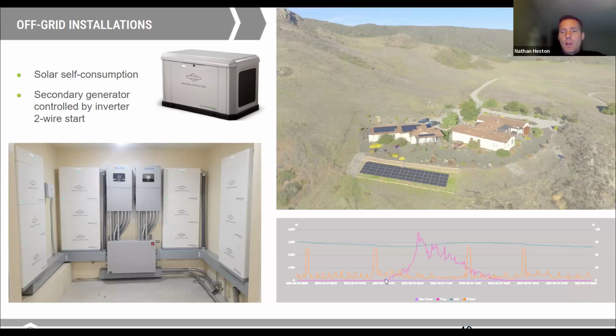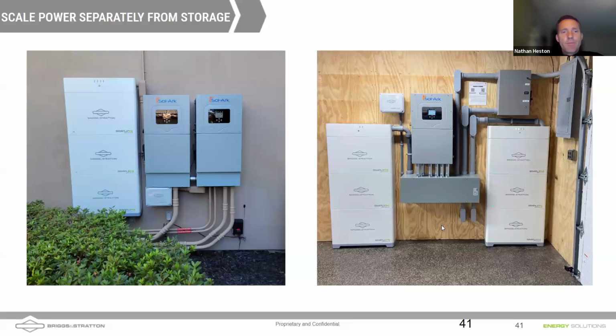And so you're seeing an example of the generator power, PV power. Generator is essentially just off in this example. And then you can see those batteries. There's not much discharge happening for the SoC, but you get nice monitoring through that Sol-Ark app as well. You can scale our batteries and our power sources independently. So here you can see dual Sol-Ark inverters. Maybe we're processing a large amount of solar. We just want a little bit of backup to keep the solar active if the grid goes down. Well, we can absolutely scale the power and the capacity independently of each other.